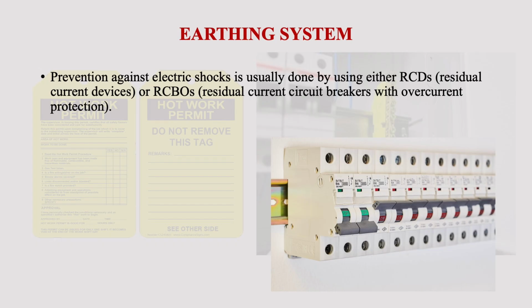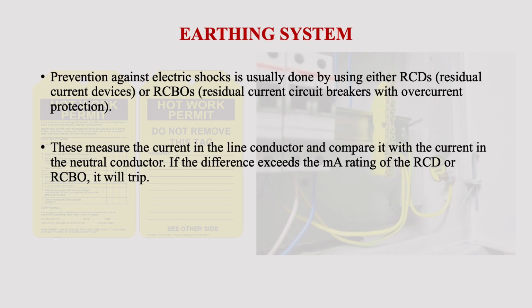This is usually done by using either RCDs, that is residual current devices, or RCBOs, that is residual current circuit breakers with overcurrent protection. These measure the current in the line conductor and compare it with the current in the neutral conductor. If the difference exceeds the milliampere rating of the RCD or RCBO, it will trip. So these two types of earth leakage protecting devices, RCDs and RCBOs, are popularly used for protection against earth leakage or electrical shock.